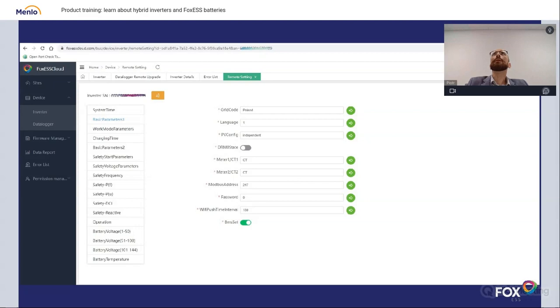DRM stands for demand response module. This will be, I believe, more and more used. It is used by the energy grid operators to remotely reduce production of PV systems. If there is a really high solar overload happening somewhere, the operator wants to have some possibility to lower the production remotely by giving a signal from one centralized point to every inverter there. So this is for turning this function on and off.